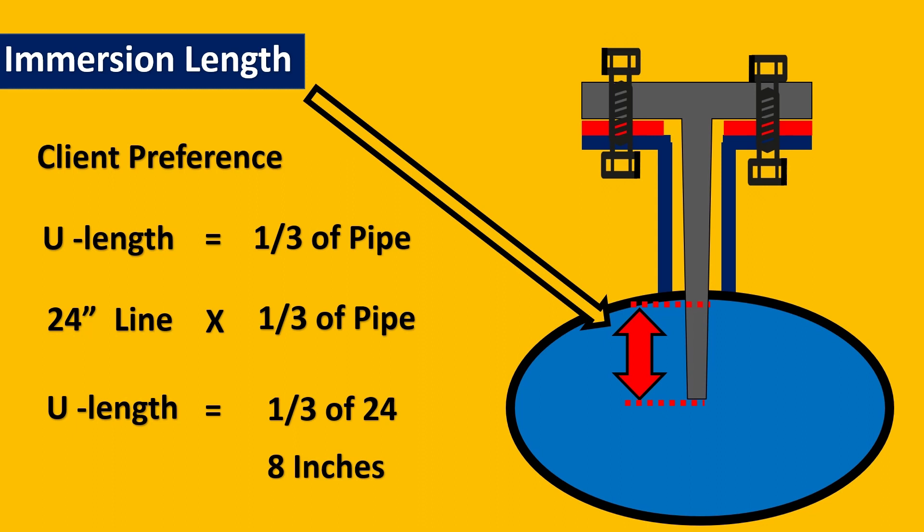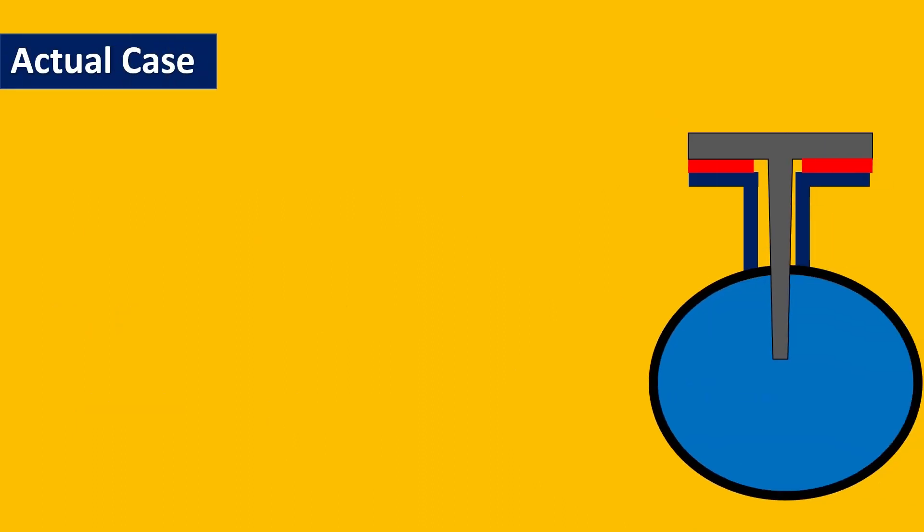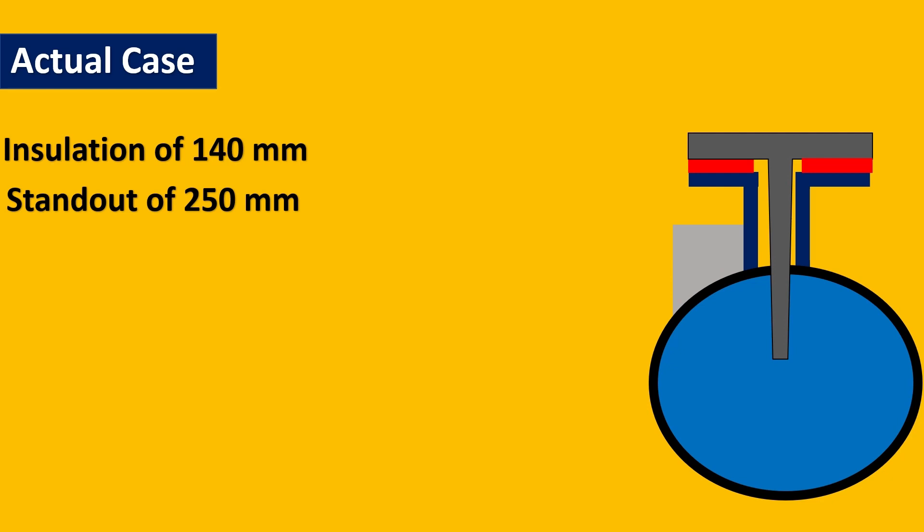Finally, let us try to actually calculate and see the case. So for example, for an actual case, here is my thermowell assembly put together. My insulation is 140 mm. So my standout I have kept as 250 mm. Why? Because I would want a clearance of around 100 mm. So going to the next standard number from 200 is 250 mm. So my standout is 250 mm. Now what I need to do is after I have got a clearance of 100 mm, what will be my immersion length?